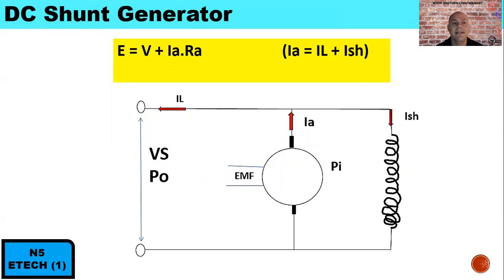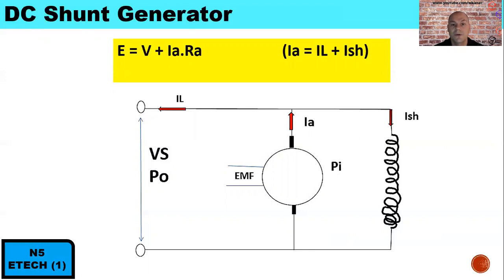The next concept covers DC shunt generators and DC shunt motors. For a shunt generator, it produces armature current and supplies load current, with a small amount of current running through the shunt winding. For a generator, the EMF is always in the same direction as the current, so it is always positive. The generated EMF equals the terminal voltage plus the volt drop across the armature.